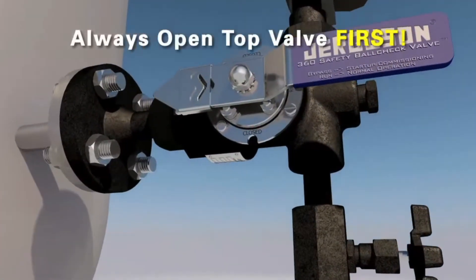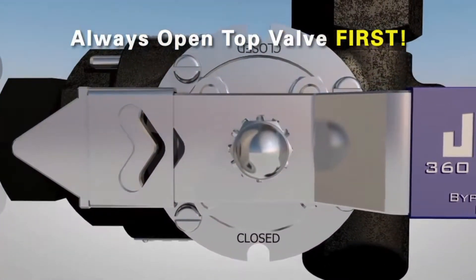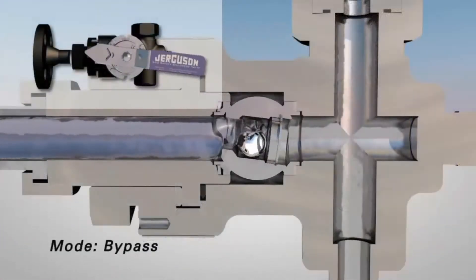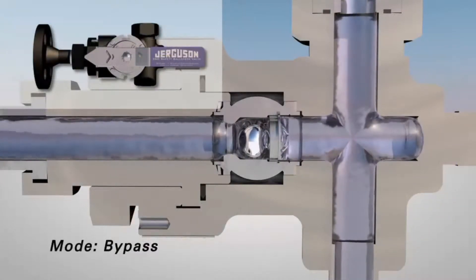It is best practice to always open the top valve first when commissioning any level device. Fluid will now flow through the valve and into the glass gauge without seating the ball check.